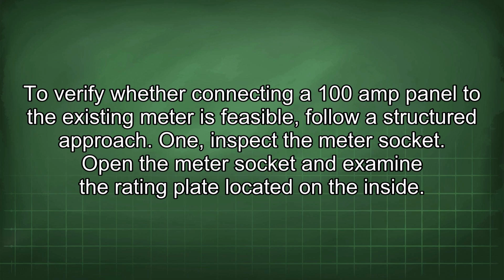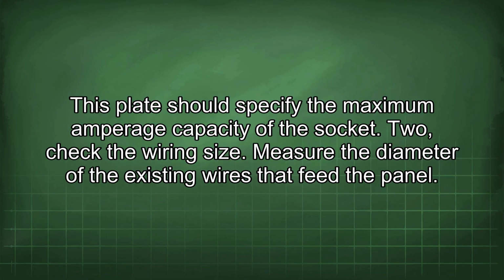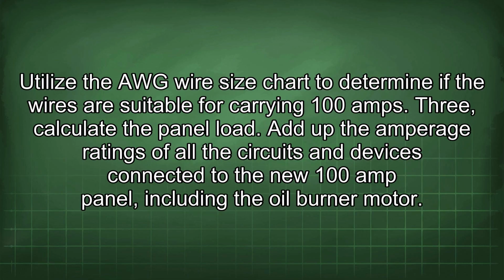1. Inspect the meter socket. Open the meter socket and examine the rating plate located on the inside. This plate should specify the maximum amperage capacity of the socket. 2. Check the wiring size. Measure the diameter of the existing wires that feed the panel. Utilize the AWG wire size chart to determine if the wires are suitable for carrying 100 amps.